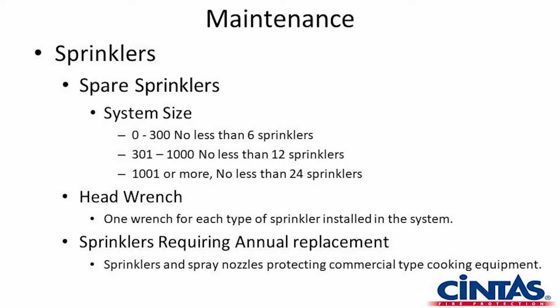If we have a sprinkler system that has 0 to 300 sprinklers, there shall be no less than 6 sprinkler heads in a spare head cabinet, usually located at the riser. If we have 4 different types of sprinkler heads, but still have less than 300, 6 sprinklers really will not do what we're supposed to do. For each type of sprinkler that's represented in the building, we should have at least 2 sprinklers at the ready to install in the case of a fire.